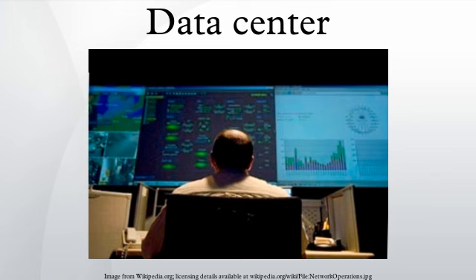Energy efficiency. The most commonly used metric to determine the energy efficiency of a data center is power usage effectiveness, or PUE. This simple ratio is the total power entering the data center divided by the power used by the IT equipment. Power used by support equipment, often referred to as overhead load, mainly consists of cooling systems, power delivery, and other facility infrastructure like lighting. The average data center in the U.S. has a PUE of 2.0, meaning that the facility uses 1 watt of overhead power for every watt delivered to IT equipment. State-of-the-art data center energy efficiency is estimated to be roughly 1.2.